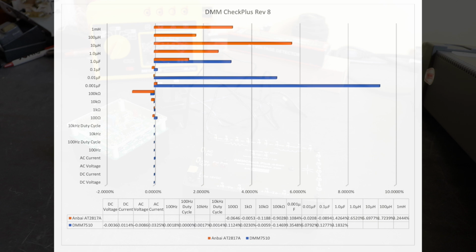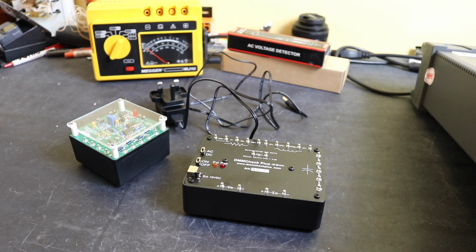The problem tends to be around those fixed values again, especially with regard to the capacitance, which is the worst one, up to 9% out on the capacitance, and then up to 5% out on the inductance. So I'm not 100% sure what's causing that really. The results from the Keithley, they could be out capacitance-wise because I think it's a 1 kHz signal, whereas the AT2817, I did set that to 10 kHz, so that should have matched the test certificate. Inductance-wise, yeah, not 100% sure.